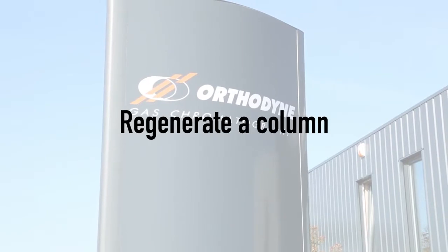To regenerate a column is a simple operation, but it's important to follow the procedure in order not to damage the material. It is important to always keep the column under gas pressure. It should never be totally disconnected for a long period.